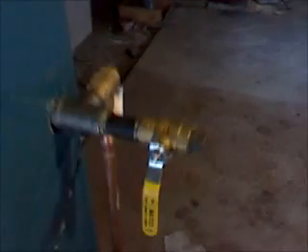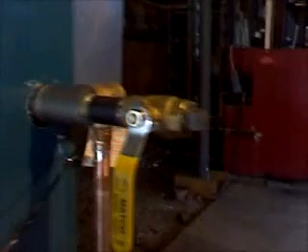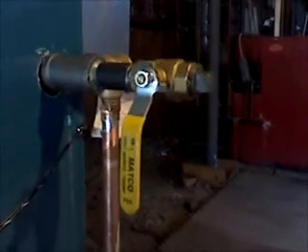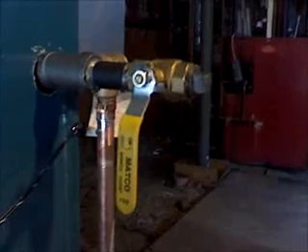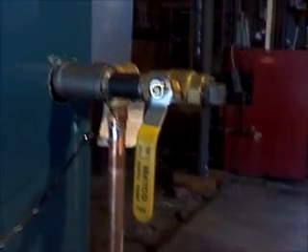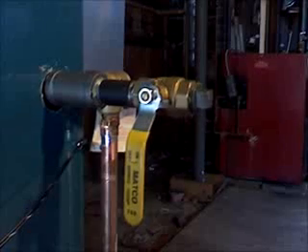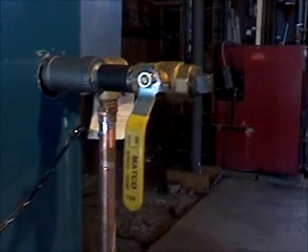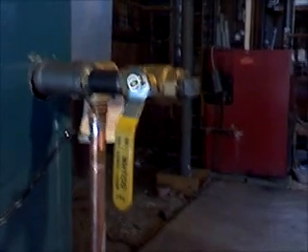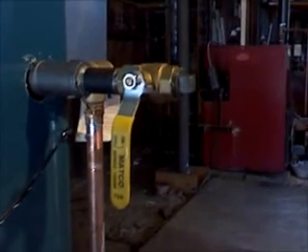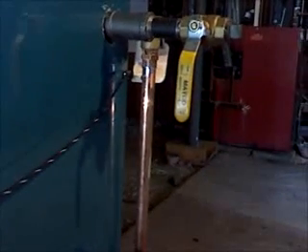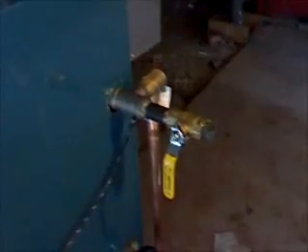Steam boilers are very dirty, and especially when you're doing a replacement, a lot of the cutting oil from the installation and a lot of the dirt from the system needs to be cleaned out of the system. But if you use some of the chemicals, it'll make the problem worse. It'll bring all the junk out of the pipes back to the boiler. So the best way to clean the steam boiler is to just continually fill it and drain it, but you have to be careful, because if you add too much cold water too fast to a steam boiler, you can crack the cast iron.